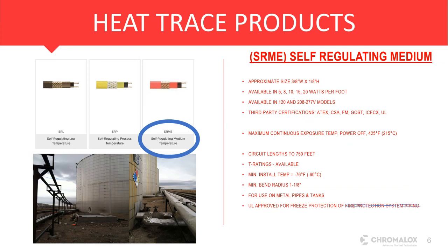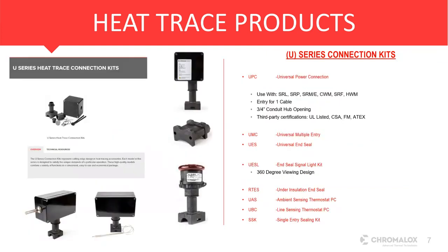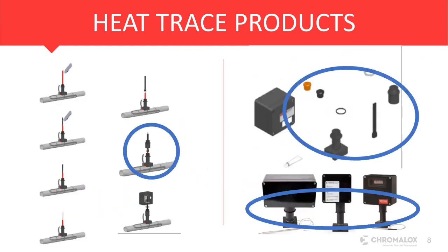From there, I would like to just highlight our connection kits. A big part of heat trace, not only is the install and layout, is how this all comes together. And we have a great line of universal connection kits, universal in the fact that we have global certifications, and they're a little unique in how they come together. We're all fairly familiar with this type of connection kit, but if you notice on the next slide, we have a grommet connector. So basically that grommet gets sandwiched with the heat tracing. It negates the need to have teeth in the standoff. You don't have weep holes for water ingress or any of that stuff. It seals the product and allows for accessibility and ease of installation. So I always like to point that out to everyone when you're using the Chromalox line of connection kits.